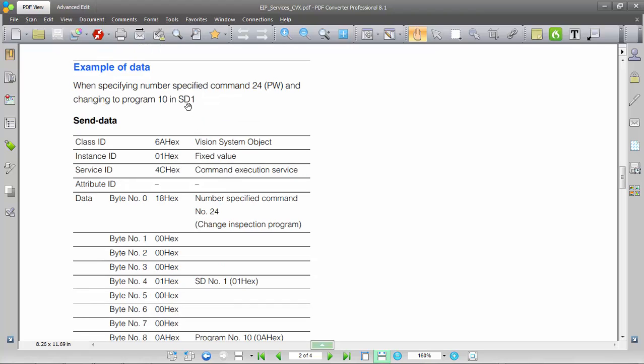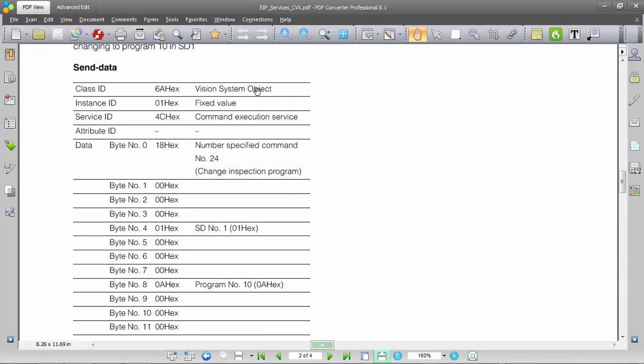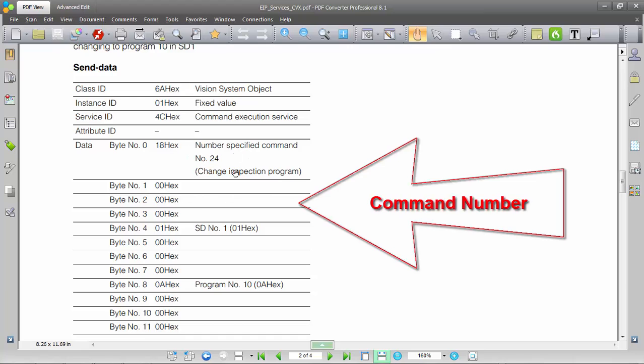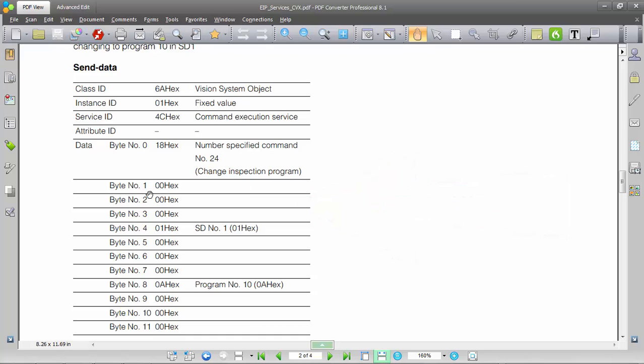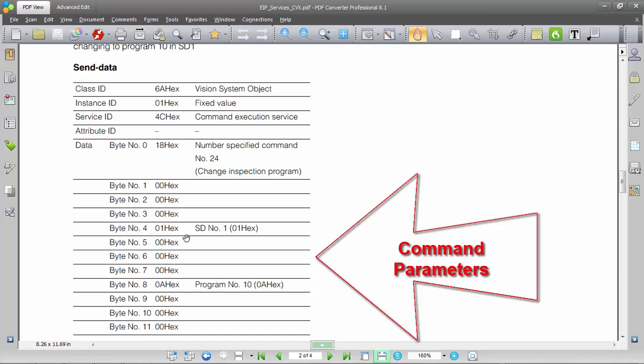In this example we're going to use the change program command, which is command number 24. All commands have a command number associated with them, and that's going to be the first four bytes that you're sending. Everything you send is going to be 32 bits, so four bytes. The first one is the command number, and then the following bytes will be the command parameters depending on the command you're executing.